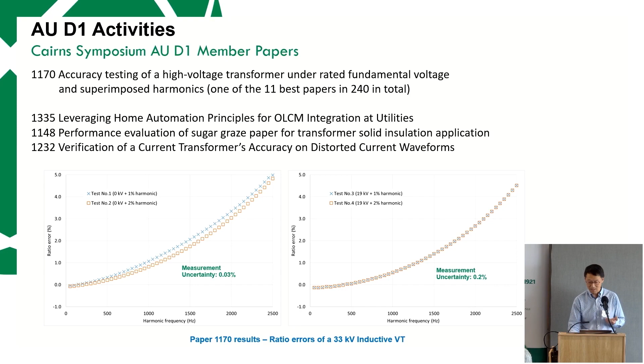Another important aspect - this paper thoroughly assessed the measurement uncertainty. At low voltage it's very low, of course, since the frequency component there is dominant. When you superimpose on the very high voltage, the uncertainty increases, but it's still 0.2%, which would be sufficient for most harmonics in most applications. That's a very good paper.